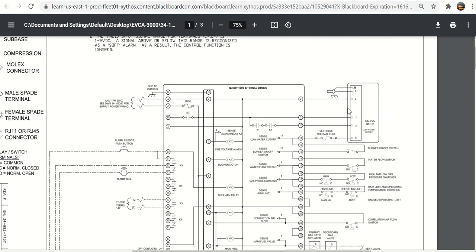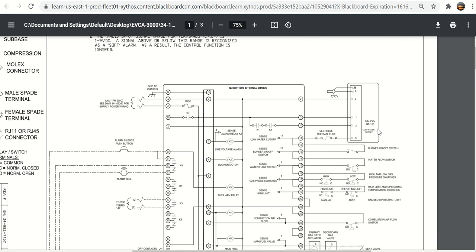Here is the low water cutoff, the McDonnell Miller 750 MT120. If you type that into Google search, it will come up. McDonnell Miller 750 electronic low water cutoff. Just like any electronic low water cutoff, it has to read conductivity through the water. You have a neutral, a hot, and then you have your switching circuit.